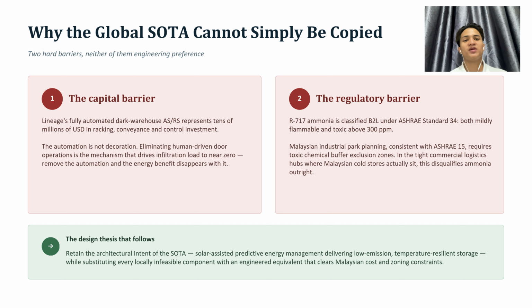So why can we not just copy Lineage Logistics directly? Two reasons. First is money. Their fully automated warehouse costs tens of millions of US dollars just for the robots and racking system. That is not something an SME cold storage company in Malaysia can afford. Second, safety rules. They use ammonia refrigerant, which is toxic and can catch fire under certain conditions. Under Malaysian safety standards, if you use ammonia, you need a large buffer zone around the building, away from other buildings. But most Malaysian cold storage sites are inside busy industrial parks, so there is not enough space for that buffer zone. So ammonia is simply not realistic for us.